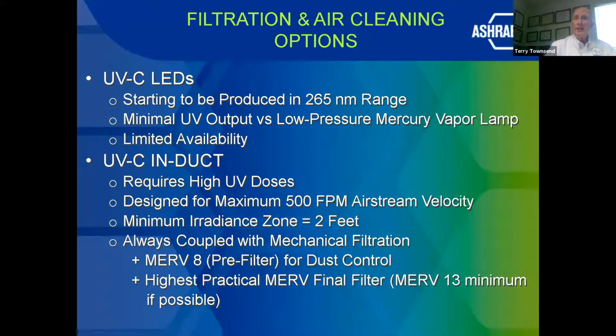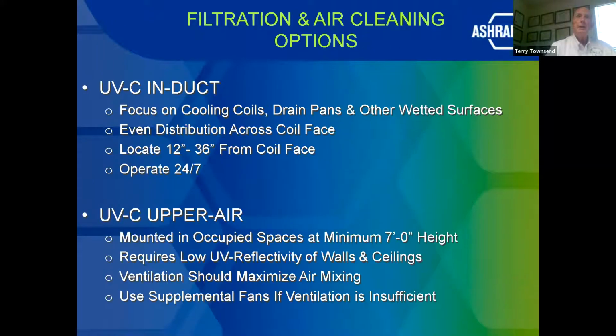UVC in duct requires high UV dosages and requires that the maximum airflow rate in the duct is 500 feet per minute. The irradiation zone for UVC to be operable is a minimum of 2 feet. It's recommended that UVC be coupled with a minimum MERV 8 pre-filter with dust control, and then the highest practical MERV final filter, again MERV 13, is what is recommended. With UVC in duct, you focus on the cooling coils, drain pans, and other wetted surfaces, and you want to locate it 12 to 36 inches from the coil face, and they should operate 24/7.